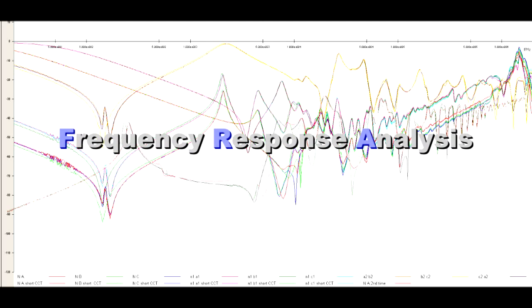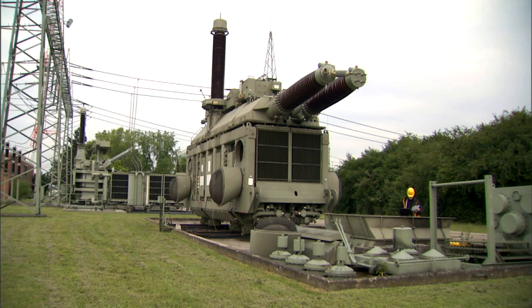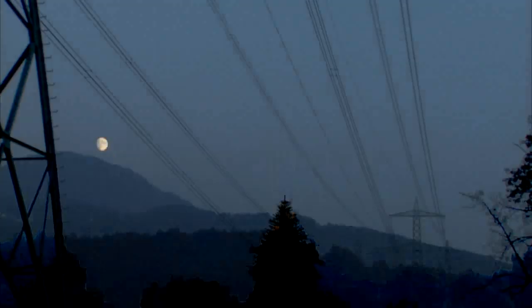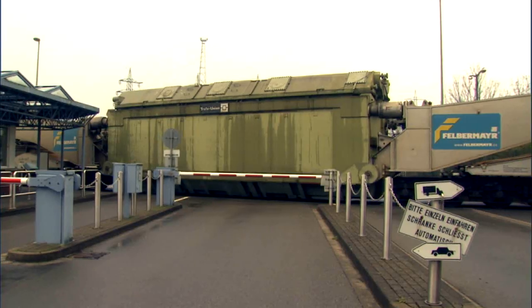Frequency Response Analysis, or FRA, is a powerful tool to ensure the integrity of a power transformer. It is typically used to detect if the core and winding assembly has electrically or geometrically changed due to a short circuit fault or a relocation.